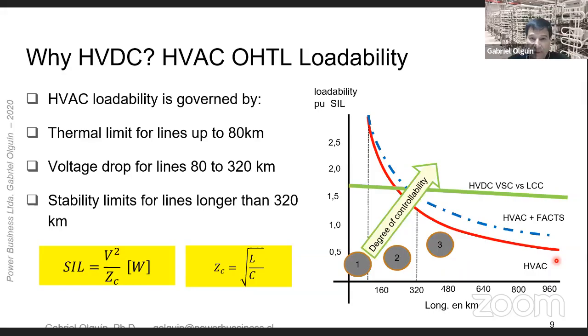The concept was first introduced by St. Clair in 1953, who developed transmission line power transfer capability curves covering various voltage levels and line lengths up to 645 kilometers, based on practical consideration and experience. Later, those loadability curves were analytically derived. Since the loadability of an overhead transmission line is expressed as per unit of the SIL, the loadability curve is universal.